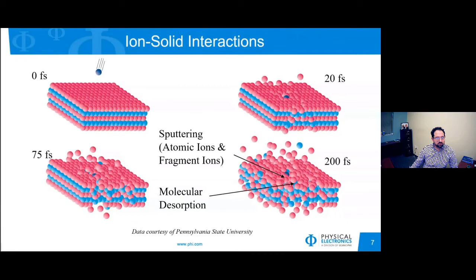Some basic principles of the time of flight process. It takes a pulsed primary ion beam to bombard your sample, and secondary ions are generated. They're extracted at 3 kV, and the primary ion beam is pulsed at around 5 to 25 kilohertz, generally around 10 kilohertz. All the secondary ions are formed at essentially the same time, time 0, in less than 1 nanosecond, and they're extracted at 3 kV, so they're all traveling at essentially the same energy.